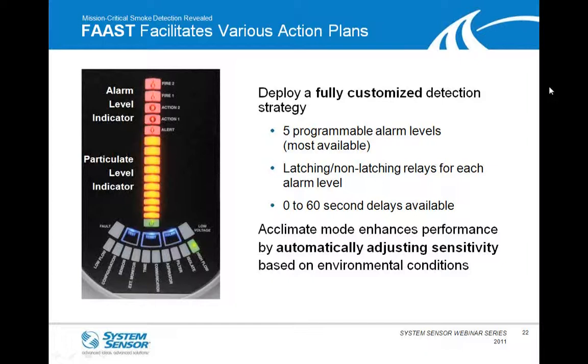And we'll talk about why you're able to do that with FAAST versus maybe some other products. And then finally, we haven't really got into false alarm immunity and sensitivities yet, but FAAST does also offer an acclimate mode, like many of our other spot type detectors, that automatically adjusts the sensitivity based on your environmental conditions. And as I talked about at the onset, these mission critical data center facilities are evolving drastically when it comes to both their HVAC systems and how they're cooling the equipment. That environment isn't necessarily static from hour to hour, day to day. It's changing, ebbing and flowing, and the acclimate mode is greatly suited for those types of applications.